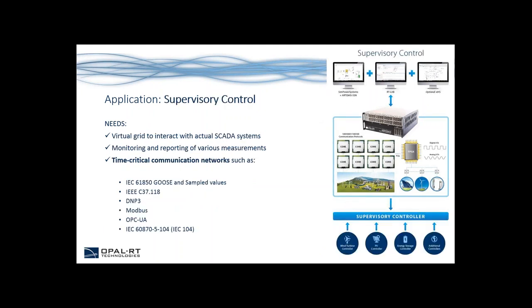The second application is supervisory control, where instead of interfacing the real-time simulation with controllers directly, we interface with a supervisory controller or SCADA system. The virtual grid is simulated and interacts with an actual SCADA system. We need to monitor and report various measurements, and we need to support time-critical communication networks such as IEC 61850, C37.118, DNP3, Modbus, OPC, and IEC 104 — all integrated for supervisory control.